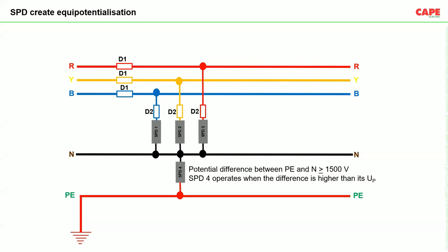Now we have installed an SPD. This particular potential difference is more than the voltage protection level of an SPD, that means the threshold voltage of an SPD. So because of this higher potential difference, SPD4 is going to operate. Once SPD4 operates, it creates a short circuit. Now because of the short circuit, this voltage which was earlier at earth will now be reflected at neutral also. So now neutral and PE are at the same potential, equipotential.